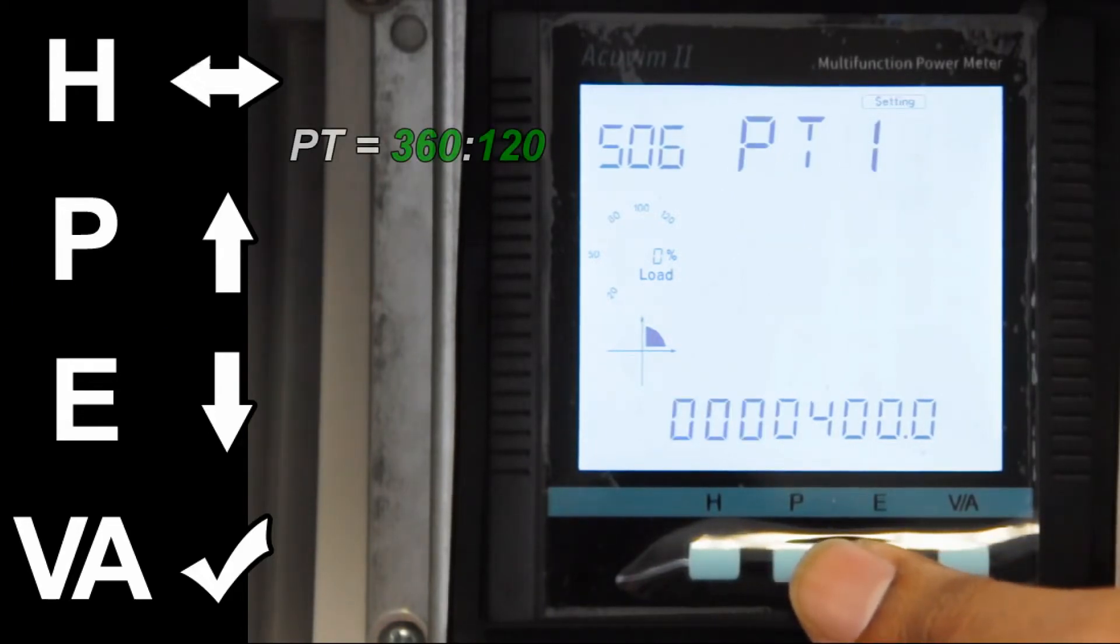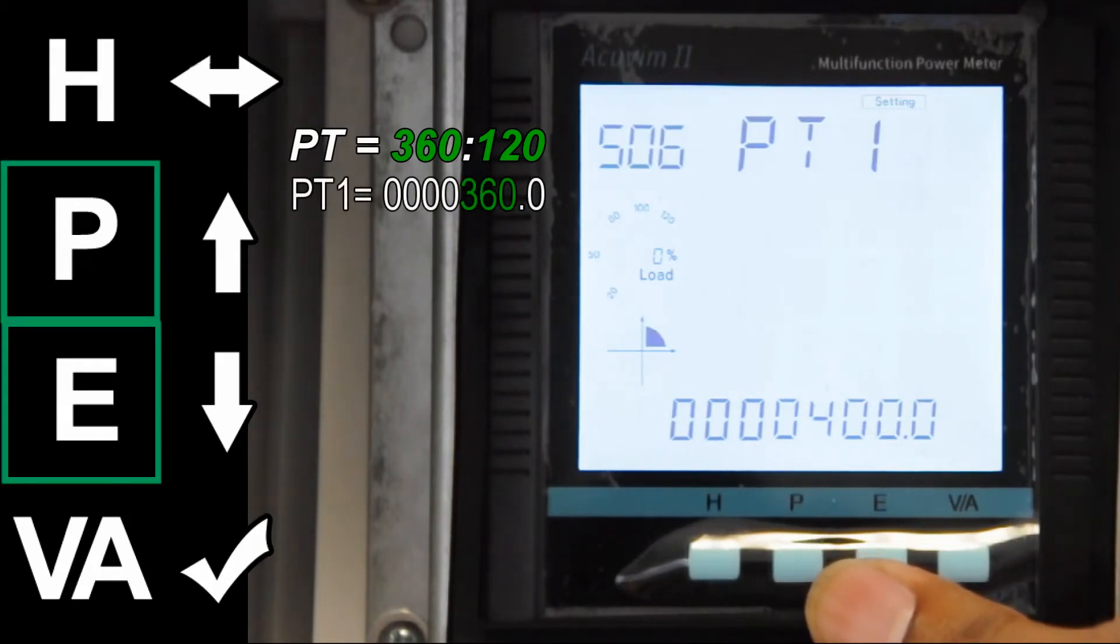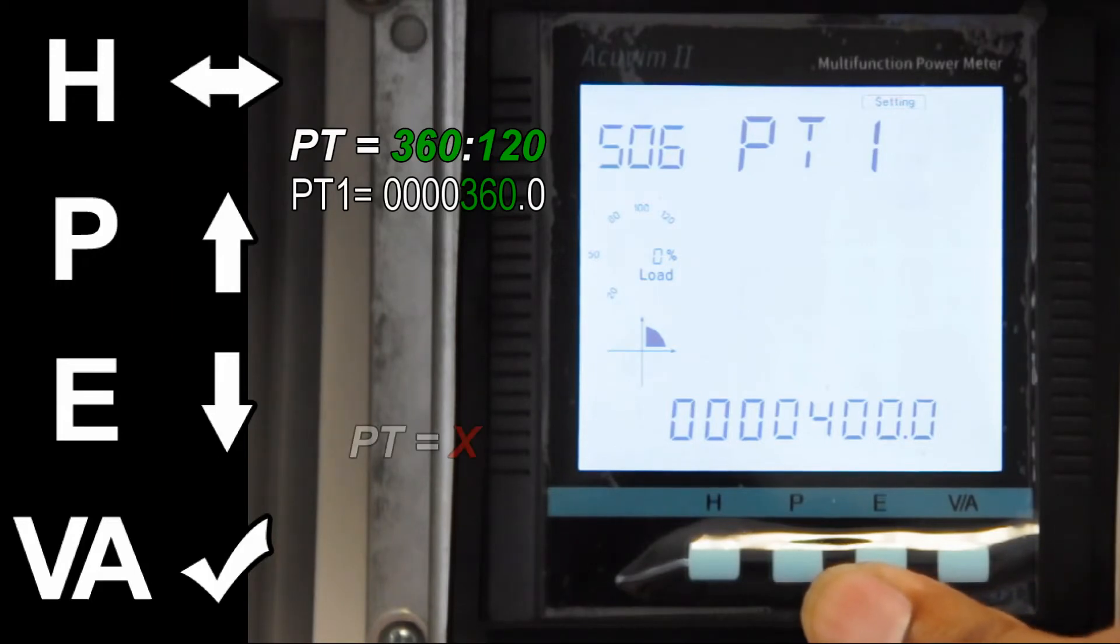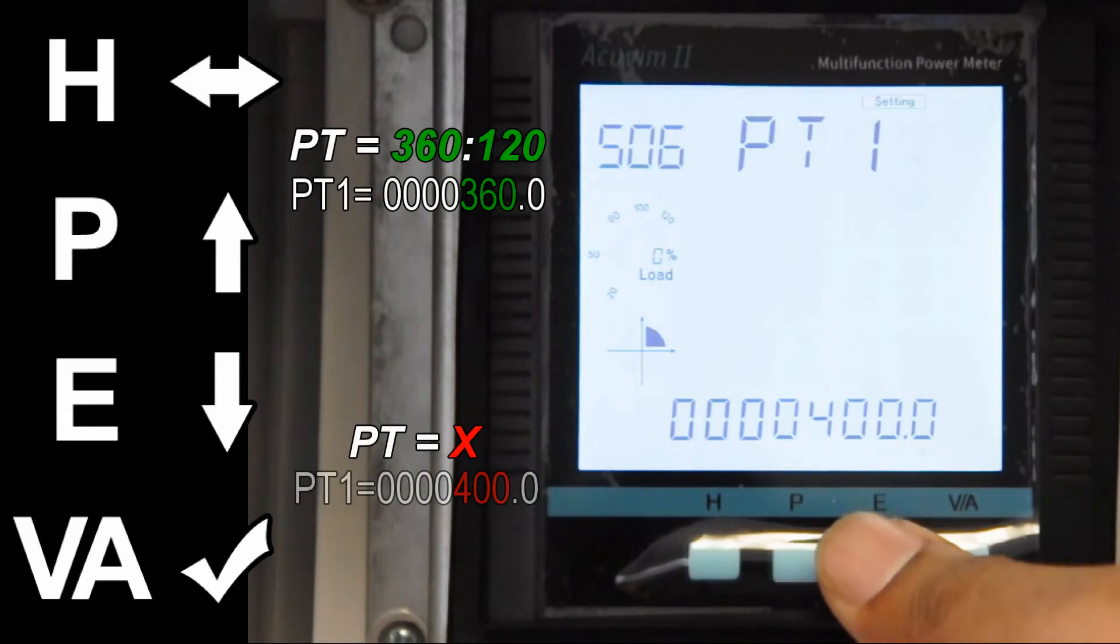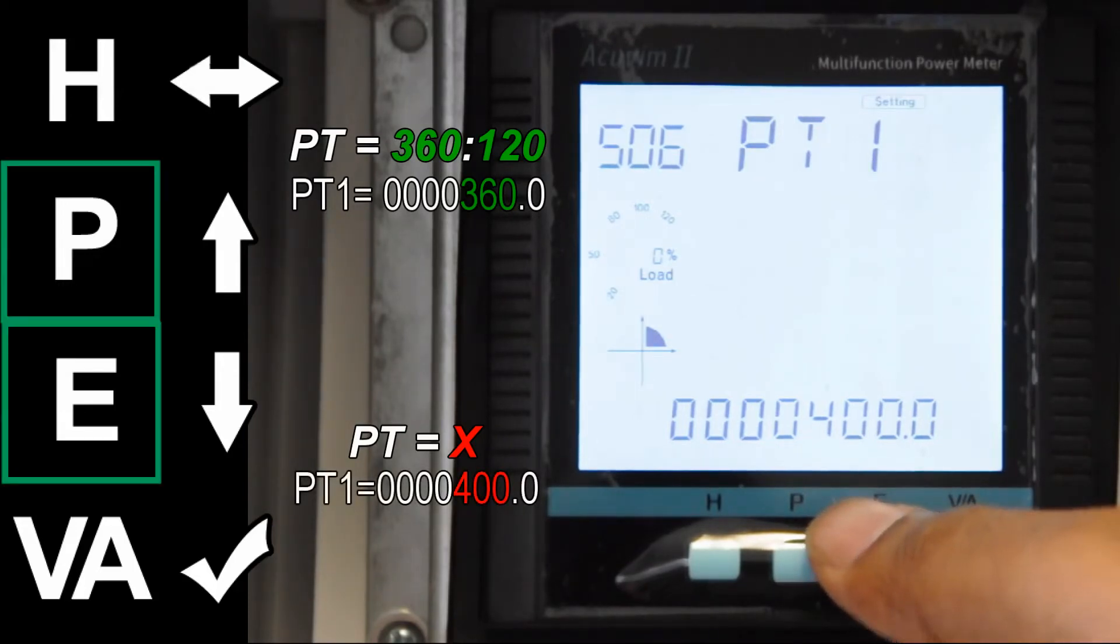If your PT ratio is 360 to 120, then set PT 1 to 0000360.0. If there is no physical PT present in the system, set PT 1 to 0000400.0.